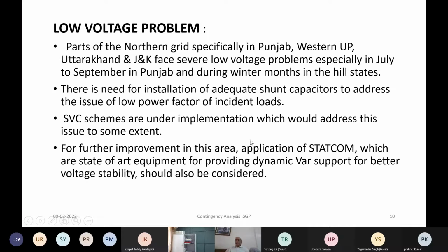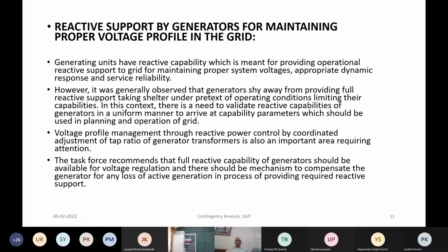SVC schemes are under implementation, which would address this issue to some extent, and further application of STATCOMs, which are state-of-the-art equipment for providing dynamic power support for better voltage stability, should be considered. Based on this recommendation, there are implementation plans for SVCs and STATCOMs. Reactive power support by generating stations we have already discussed. I will only read out the last bullet from the report, which says that the task force recommends that full reactive capability of the generator should be available for voltage regulation, and there should be a mechanism to compensate the generators for any loss of active generation in the process of providing required reactive support.